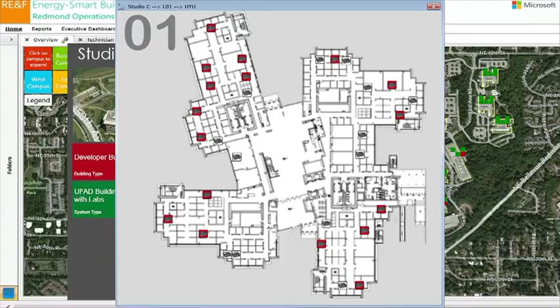This was Sunday, a screenshot I took. On Sunday at 12:15, just after midnight in Seattle time, this terminal unit came on. It shouldn't be coming on—it's a priority 5 space, a very low risk space—and it's wasting $169 a year. Well, $169, Daryl, that doesn't sound like very much.